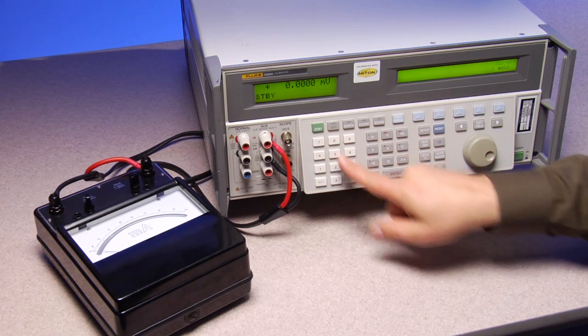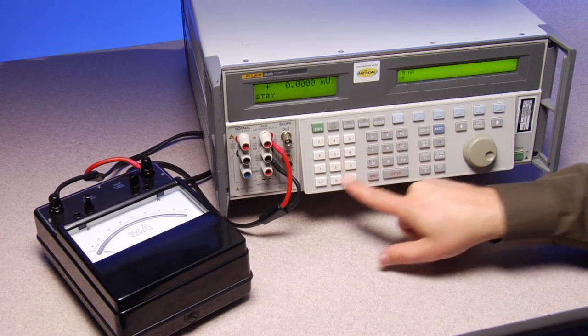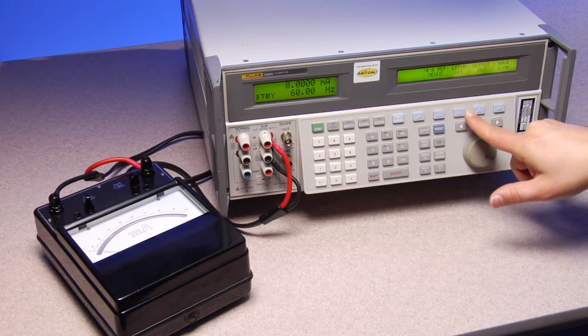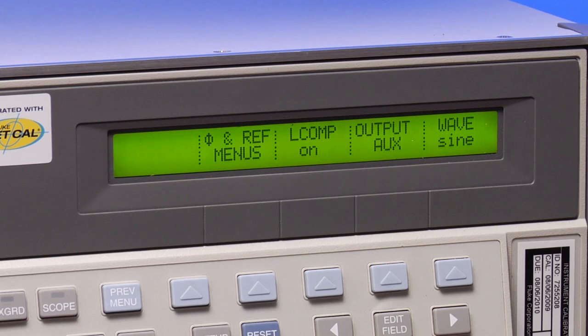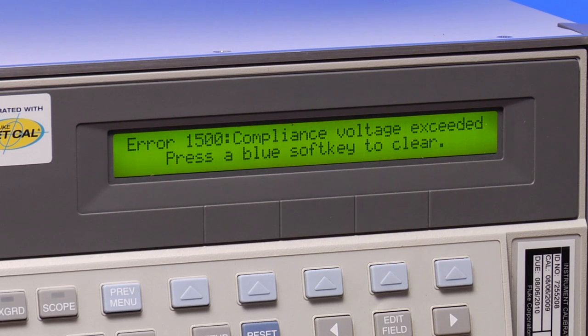The 5080A is a new type of calibrator with high compliance to calibrate low impedance analog meters. In the past if you used a calibrator like the 5520A to calibrate this type of analog meter it might trip and give you an error message, compliance exceeded.